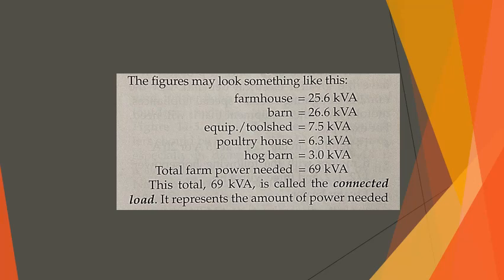Do not forget to consider future growth, which would demand an increase in power conditions. Thus, the sizes of service conductors should be at least one size larger than the ones calculated. In this case, 4 AWG would be the minimum, but a wiser choice would be 2 AWG or 1 AWG. Without a doubt, this would be a very small farm.